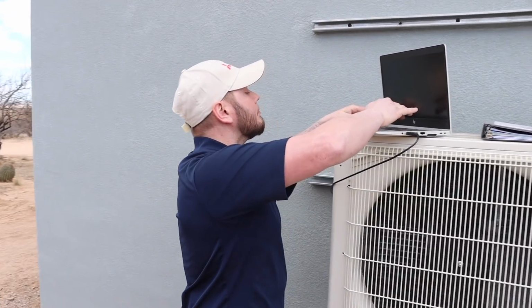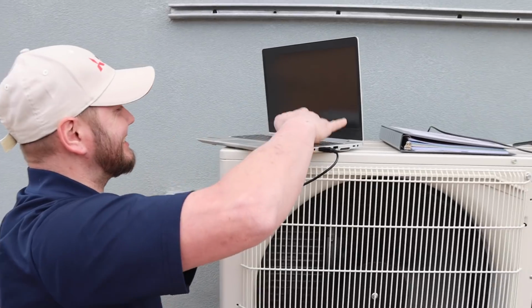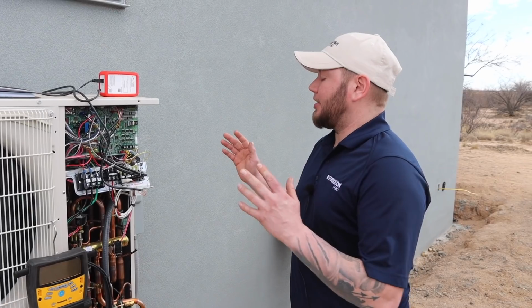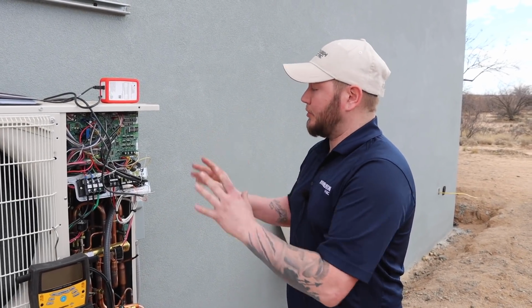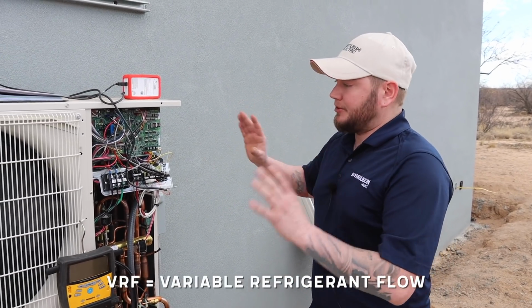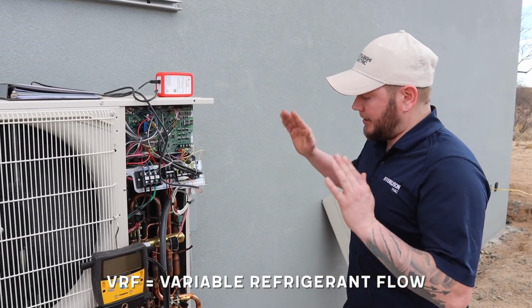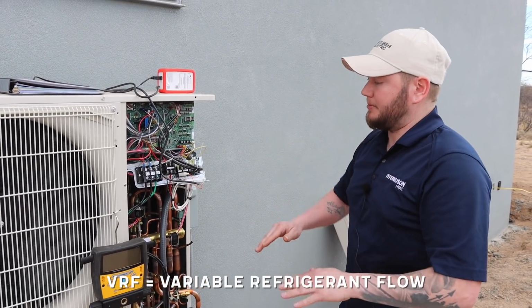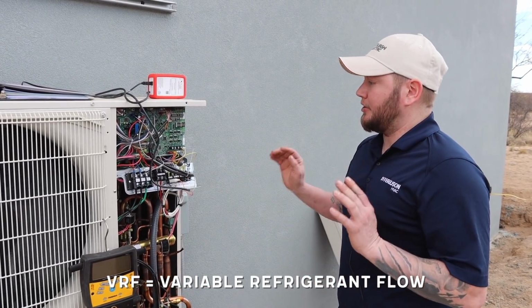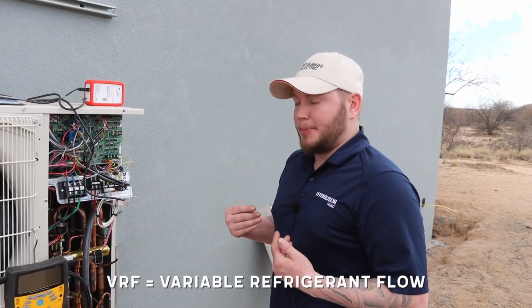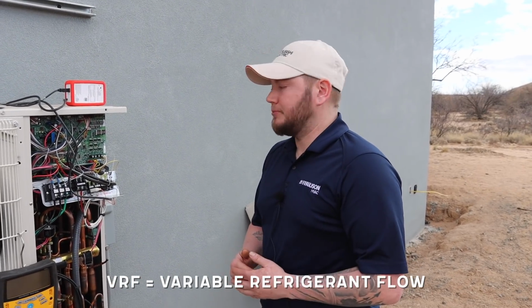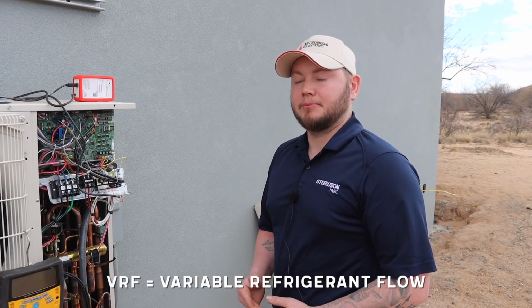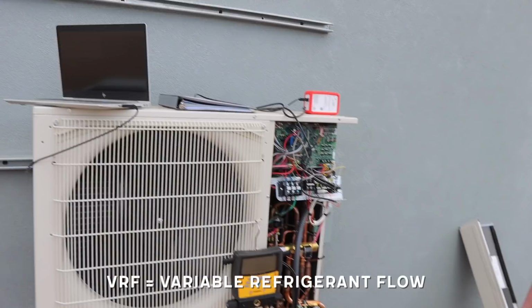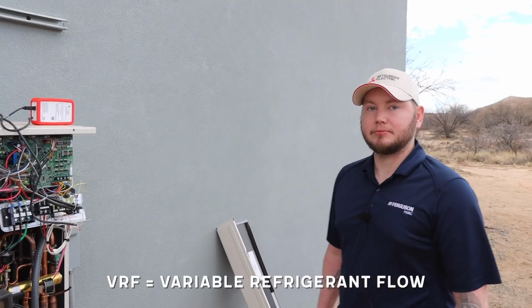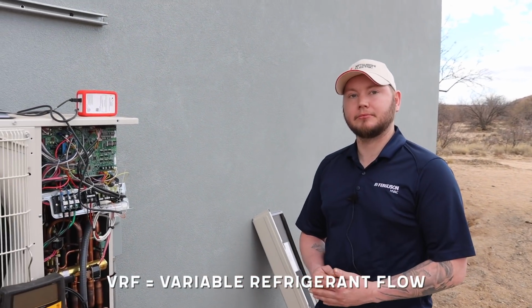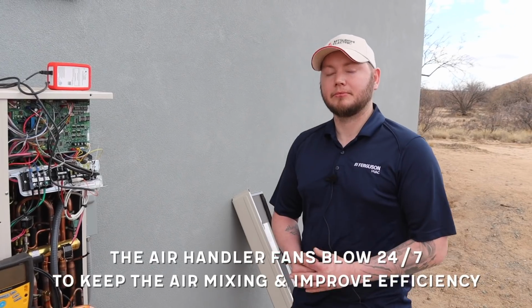So now we got the nerd here. He's got the computer out. In all of our systems, the outdoor unit's control board controls everything. It takes every single demand that the indoor unit has, and it uses an algorithm to ramp the compressor and the fan motors up or down in order to achieve what we're asking for. So that's with the Mitsubishi system, with the VRF system, yes. It's for variable refrigerant flow. So instead of the system just cranking on and blowing really hard at periodic times throughout the day, the fans are actually running 24/7. Correct.